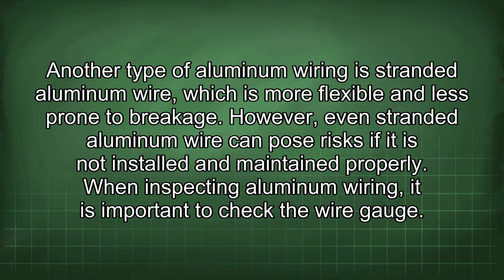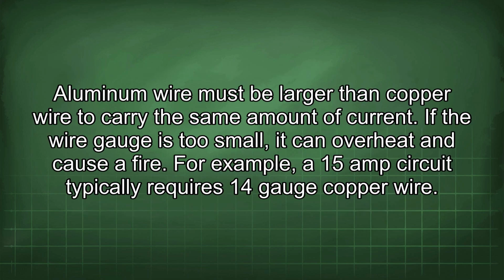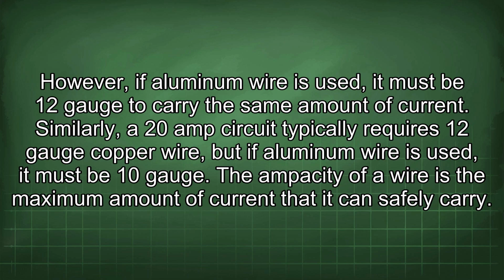When inspecting aluminum wiring, it is important to check the wire gauge. Aluminum wire must be larger than copper wire to carry the same amount of current. If the wire gauge is too small, it can overheat and cause a fire. For example, a 15 amp circuit typically requires 14 gauge copper wire. However, if aluminum wire is used, it must be 12 gauge to carry the same amount of current.